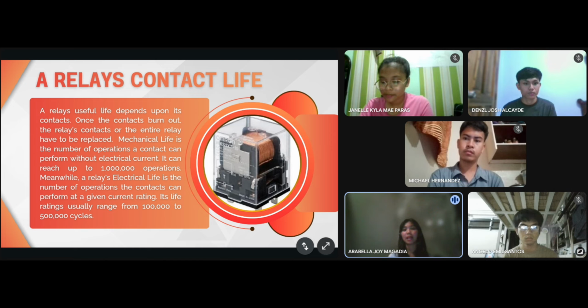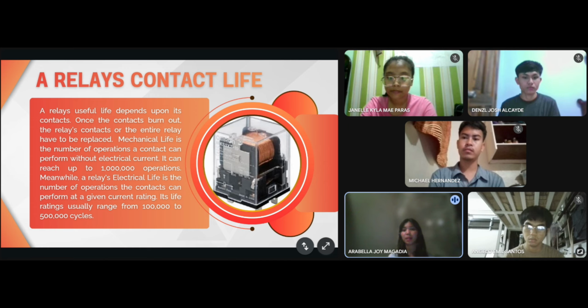Next, we have the electrical life. This one is more practical. It measures how many times the relay can operate under actual electrical load, meaning when current is flowing through it. Because electricity causes heat and sparks every time contacts open and close, the electrical life is shorter than the mechanical life. Typically, a relay's electrical life ranges from 100,000 to 500,000 cycles depending on the current and voltage it's handling.